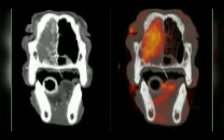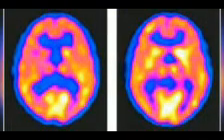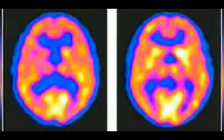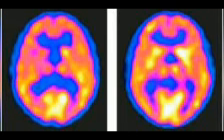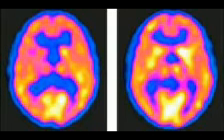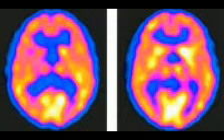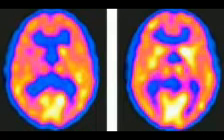directions. These are detected when they reach a scintillator in the scanning device, creating a burst of light which is detected by photomultiplier tubes or silicon avalanche photodiodes, SiAPD. The technique depends on simultaneous or coincident detection of the pair of photons moving in approximately opposite directions. They would be exactly opposite in their center of mass frame, but the scanner has no way to know this, and so has a built-in slight direction error tolerance. Photons that do not arrive in temporal pairs, i.e. within a timing window of a few nanoseconds, are ignored.